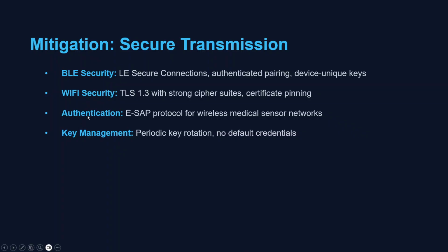And now we talk about mitigation, which is secure transmission. First of all, for Bluetooth Low Energy devices, that is BLE, we implement secure connections, the most secure BLE pairing method, so that attackers cannot attack. This uses authenticated pairing, which ensures both devices verify each other's identity before connecting. Then for Wi-Fi security, we specify strong cipher suites, and TLS 1.3 is mandatory for all Wi-Fi connections. Certificate pinning prevents man-in-the-middle attacks by ensuring the workstation only accepts certificates from known and trusted servers.